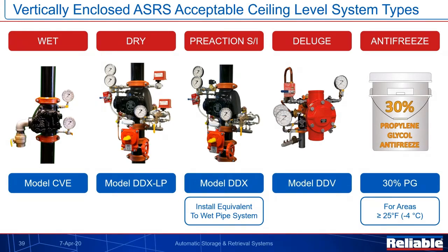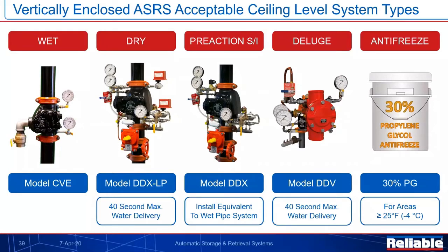Now, these two options that are new to us here, the dry and deluge, they do have a specific requirement, and that's that we anticipate a 40-second maximum water delivery time based upon four remote sprinkler heads. So that's what we need to be concerned about if we go with those two options, making sure the water delivery is timely. That way we can end up controlling and containing that fire.